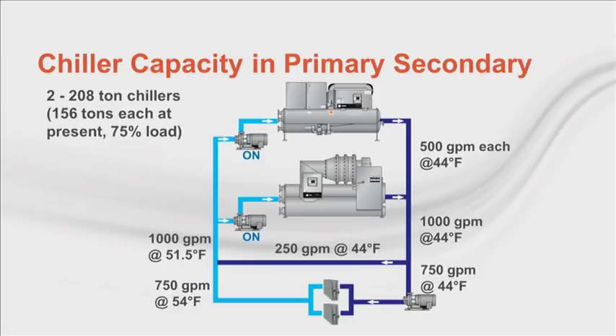We can calculate the effect this surplus water has on the temperature of the water coming back to the chillers. So let's first assume that the coils are selected for a 10-degree DeltaT, and because there are only two-way valves in the system, we might therefore always expect 54 degrees to come back to the central plant. Using the water rule that flow coming into a T always has to flow out of the T, we have 250 GPM at 44 degrees, mixing with 750 GPM at 54 degrees, giving us 51.5 degrees entering each chiller. The chiller capacity is therefore fixed by the flow times the temperature difference. In this case, we have 500 times 7.5 degrees of chiller DeltaT divided by 24 for water, and that gives 156 tons each. Since the chillers at 10 degrees of DeltaT were 208 tons, that's a 75% capacity.